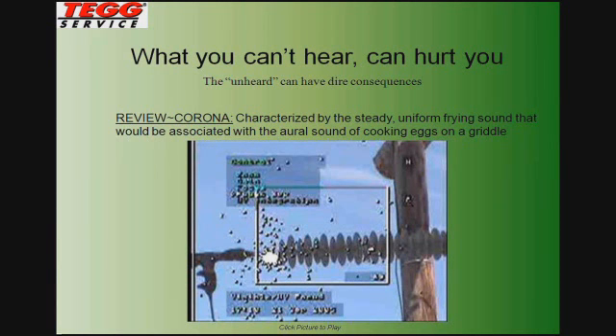With infrared, you cannot see corona, whether it's nuisance or destructive. And the reason for that is the infrared cameras are designed to operate at wavelengths of either 3 to 5 or 8 to 12 micrometers in wavelength. It's light. Whereas the corona occurs in the ultraviolet part of the electromagnetic spectrum, meaning you need a different type of imager to visualize that.